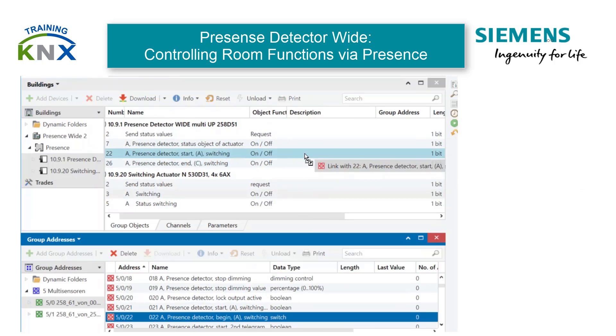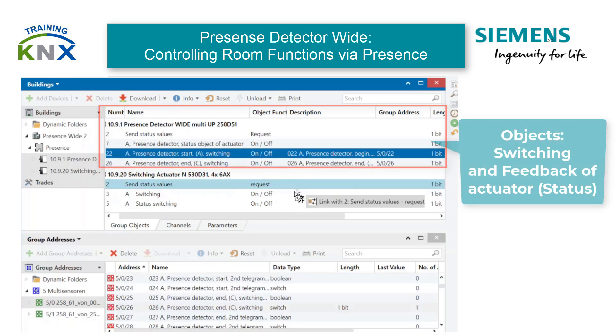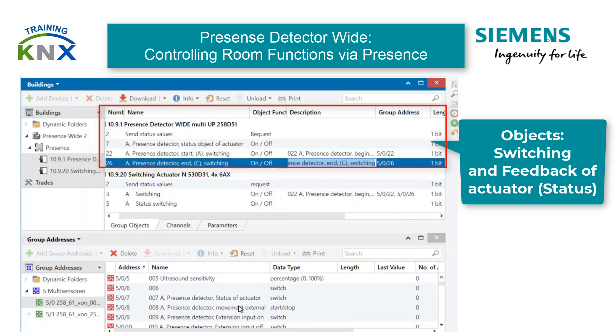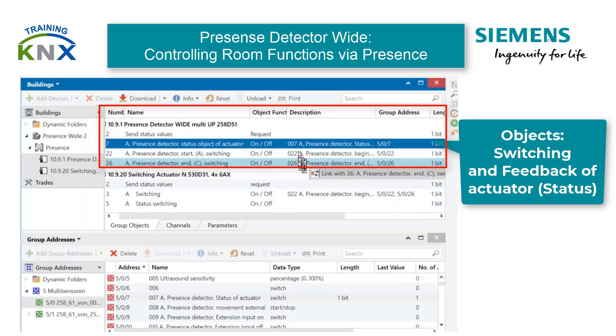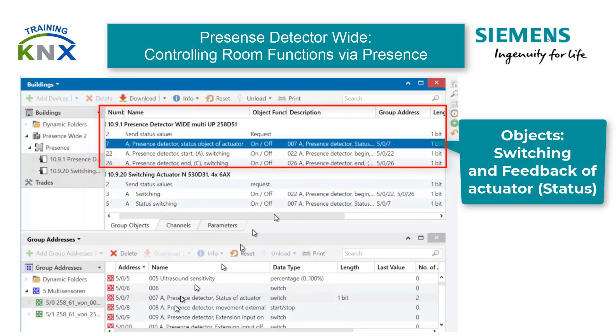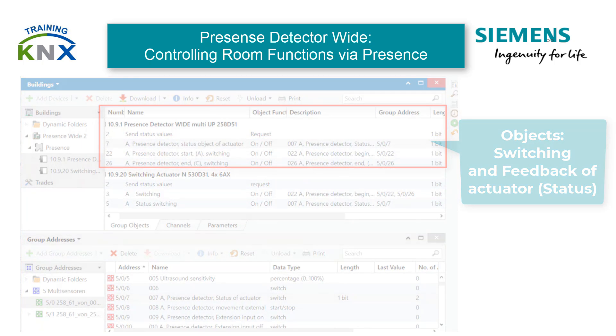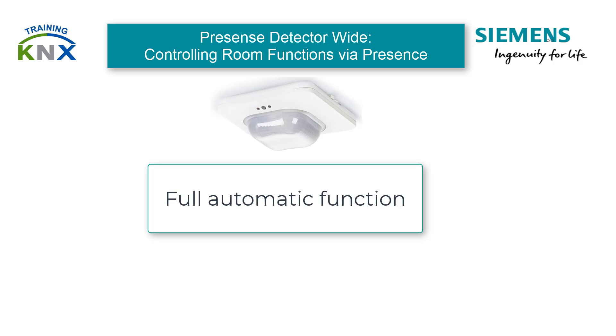It is sufficient to use it with only one group address. If a status message from the controlled actuator is available, it is useful to link it to Object 7, Status of Actuator. In conjunction with the evaluation time of the status feedback object, this can be used to ensure that the Presence Detector cannot immediately send an on-telegram again, even if lighting is switched off manually. Here we are finished with the configuration of the fully automatic, Presence Dependent Switched Lighting Control.